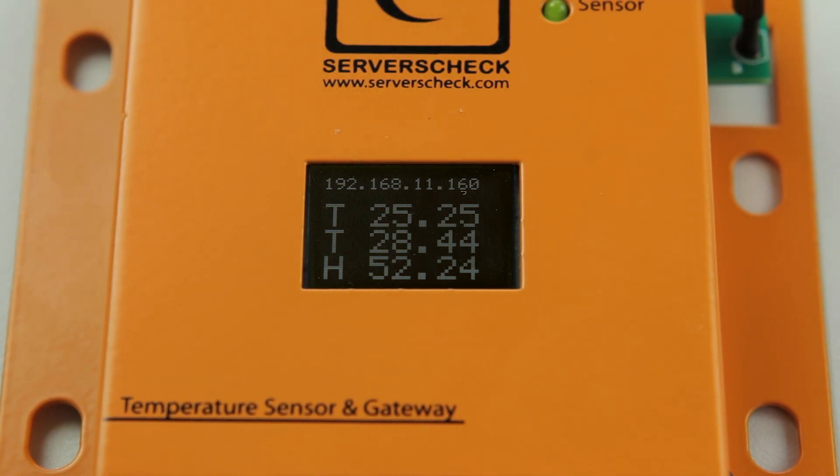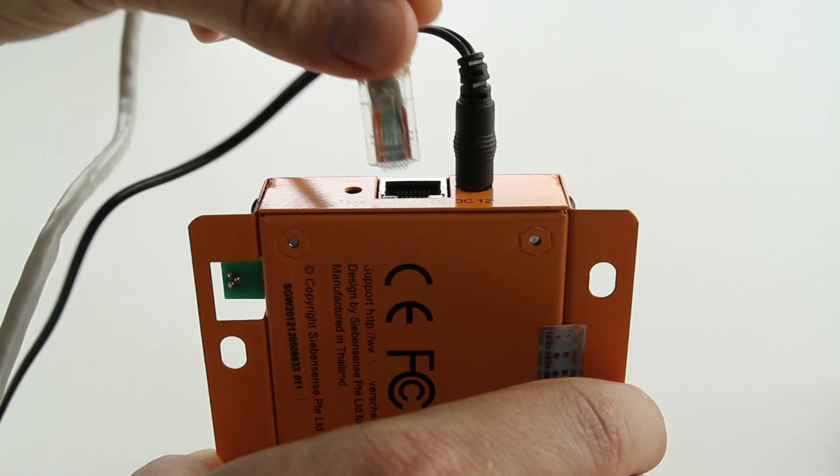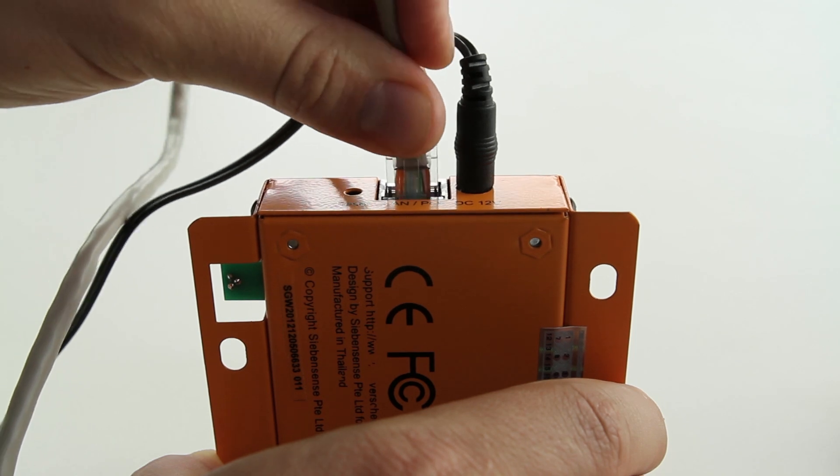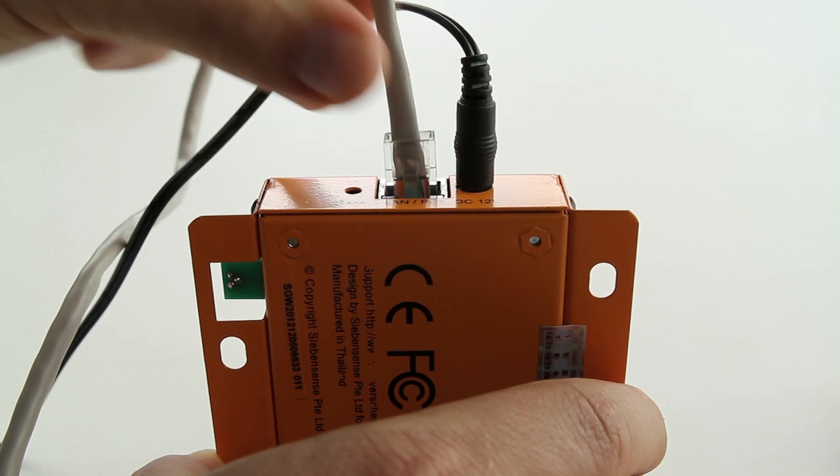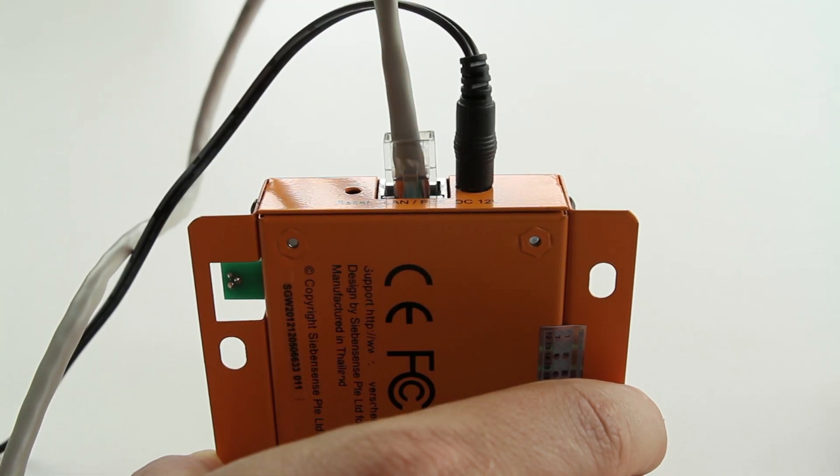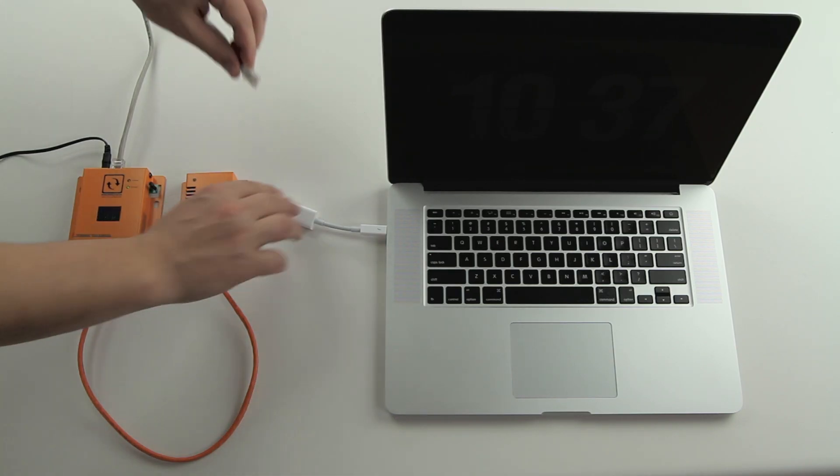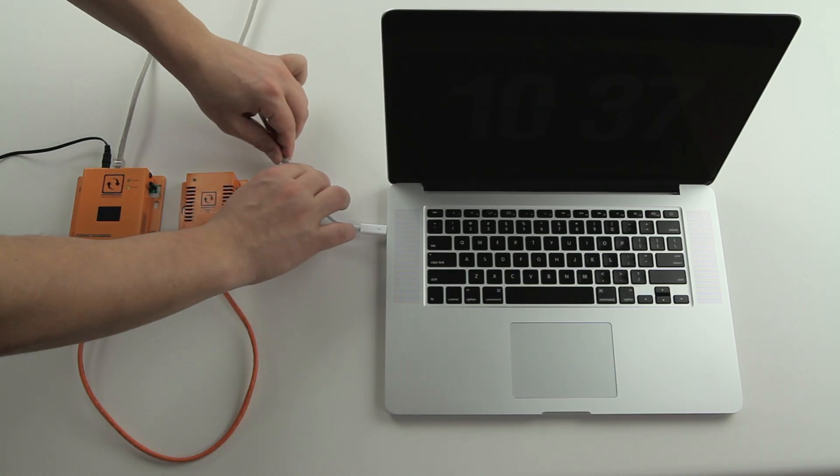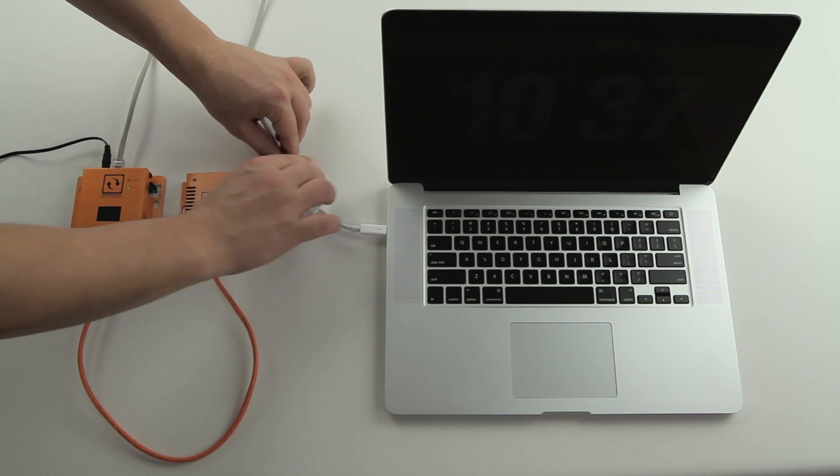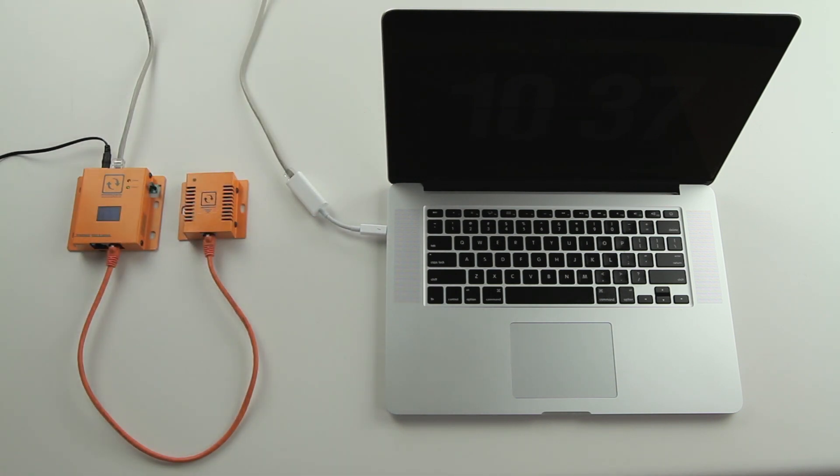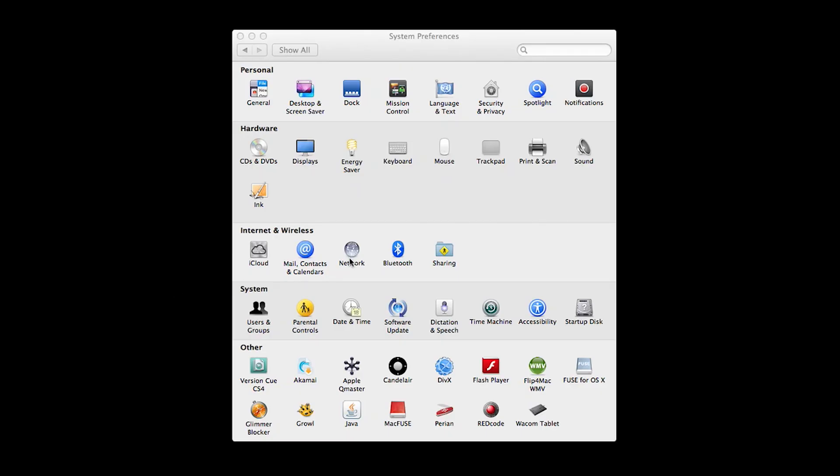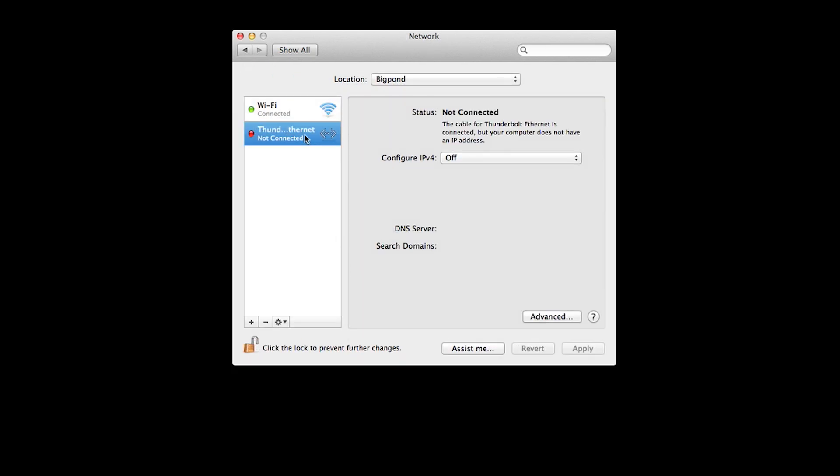The Sensor Gateway has also a built-in web server. Through any PC, laptop, or tablet you can connect to the unit. However, for initial configuration, it is best to use a PC or laptop with a wired connection. Open the network settings of your PC or laptop and change the IP address to 192.168.11.159.